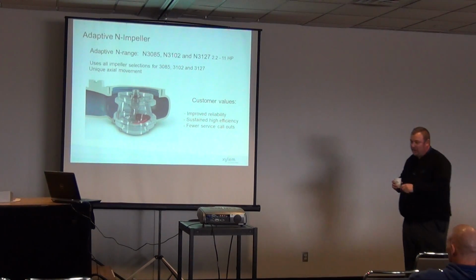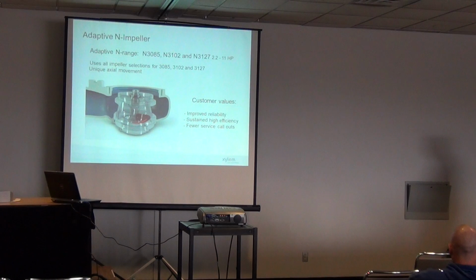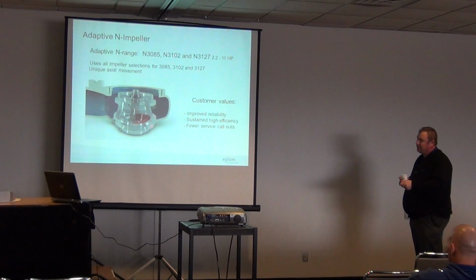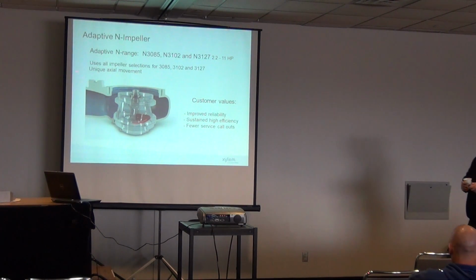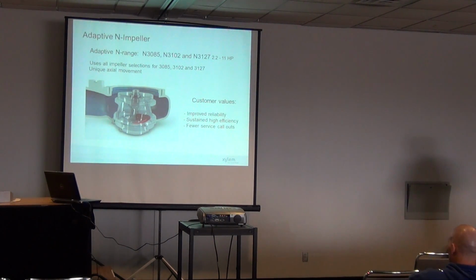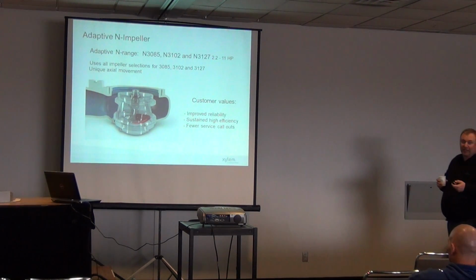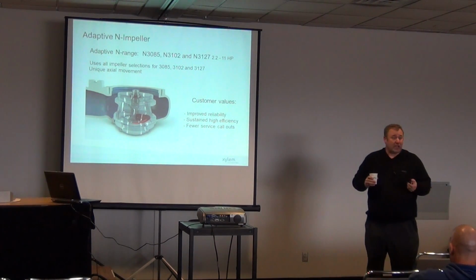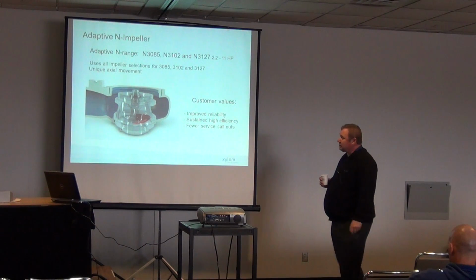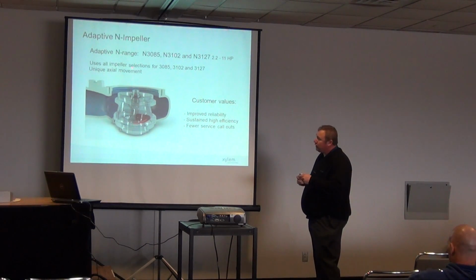Another feature that we've done as part of this system is we put what we call an adaptive N impeller in the wet end, and that's in our 3s, 5s, 7.5, and 10 horsepower, in those smaller units. This actually has the ability when a large piece of trash comes into the pump, modern trash, to raise up to 15 millimeters depending on the model. It will actually pass that material through the pump, helping those smaller horsepower pumps pass larger material through them. It also helps with savings on seals, bearings, because it absorbs shock better. And when those big materials come in, it actually raises that impeller up, shortening your shaft overhang.